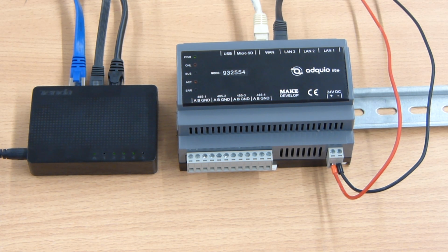As you see, in this example, we are using a switch, but being an Adquio Lite, we could perfectly use all its LAN ports. In this case, we have a connection only with Ethernet and temporarily with the laptop, so there are 2 Ethernet ports. Since Adquio has 3, we could work perfectly without this switch. We could use its LAN ports. However, we decided to use a switch for this example, as it is the closest approach that will work with all controllers, including the Adquio Mini, which has only 1 network port. If that were the case, if we were working with an Adquio Mini, all network cables would come to this switch, including the WAN cable for the internet connection.